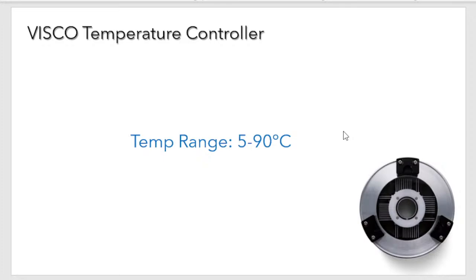The VISCO temperature controller is the main subject of today's webinar. It is important for maintaining your product at a specific temperature while taking readings — if the temperature changes, the properties of your product change, including viscosity. Keeping the sample temperature stable and at the right value is very important. The VISCO temperature controller has a temperature range of 5 to 90°C, which is sufficient to cover most confectionery needs.